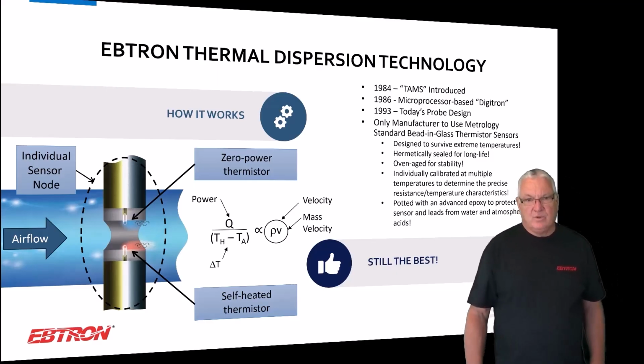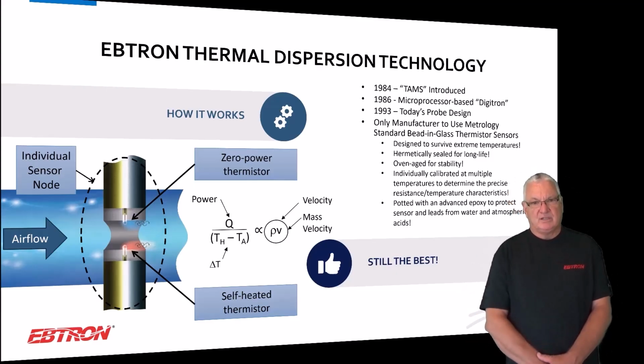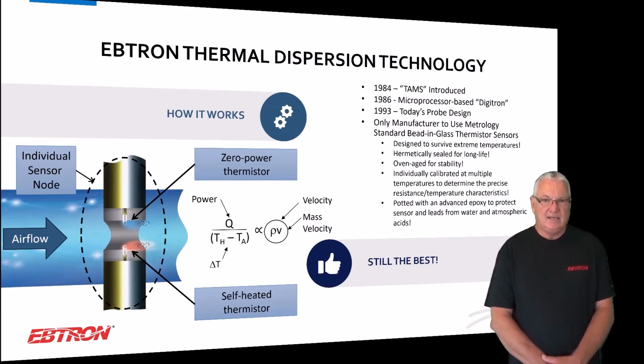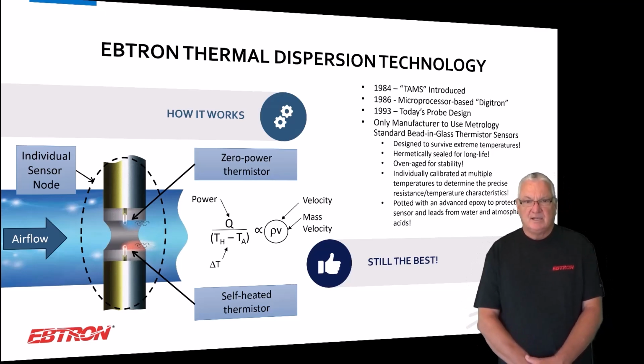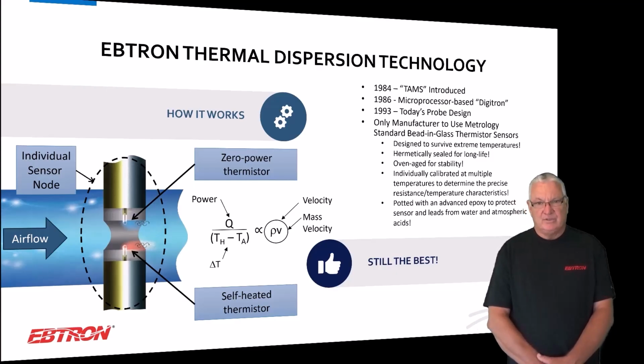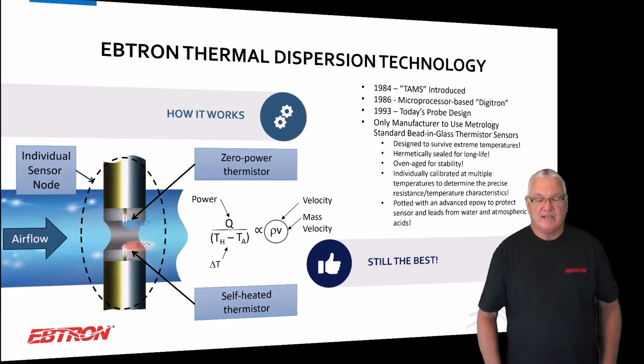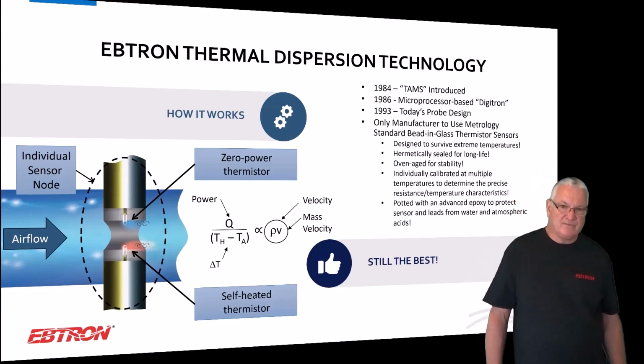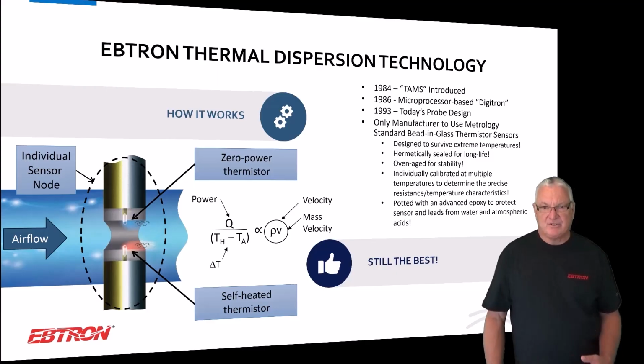Okay, and so we were real early on. We looked at this in the beginning, and the original EBTRON in 1984 was an analog circuit. Okay, and then in 1985 and 86, we released our microprocessor-based device. We're the only ones that use a bead glass thermistor, which is really a high-performance thermistor for temperature measurement. It's been designed to handle extreme temperature changes, much more than we're going to see in HVAC. They're hermetically sealed for long life. They're actually oven aged for extended periods of time.